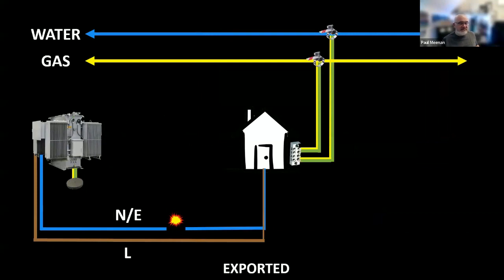On a single house, much easier in the countryside, with combined neutral earth, if you fail on the connection, then your neutral earth return has only one way to go, and that's straight down to ground. Hence, we're recommending local electrodes now as well. So that's known as exported diverted neutral current.